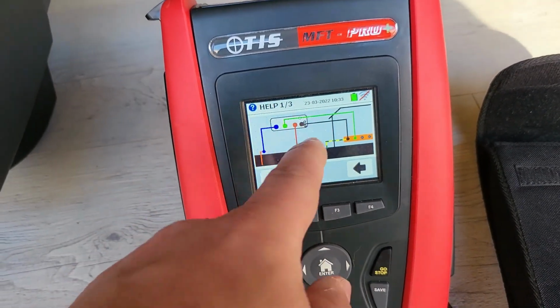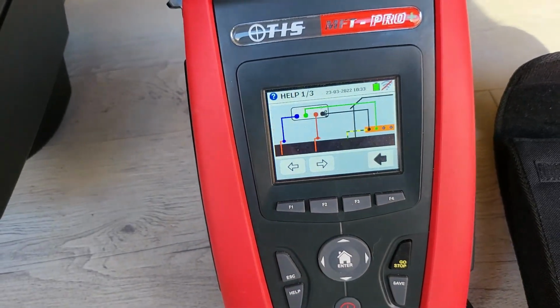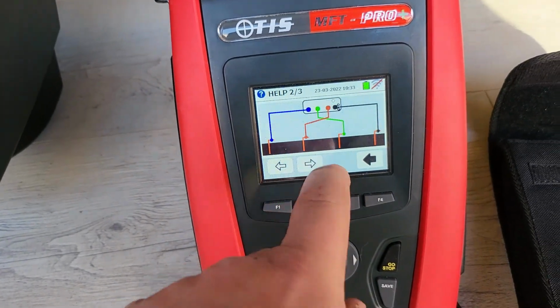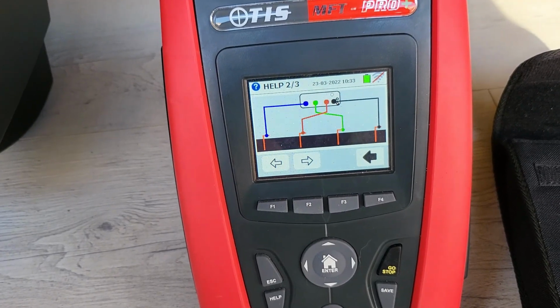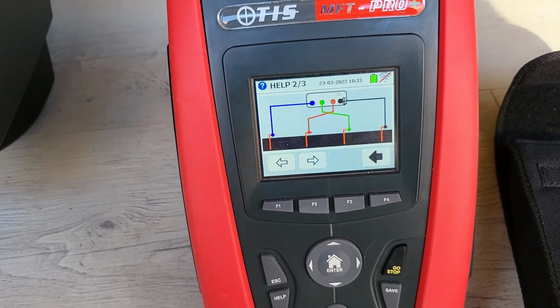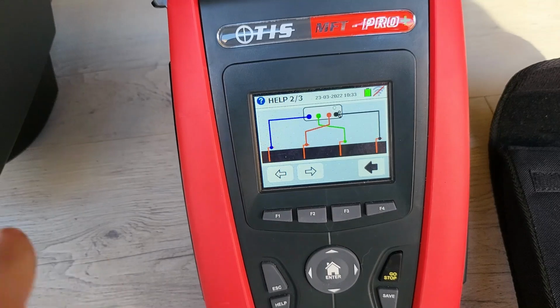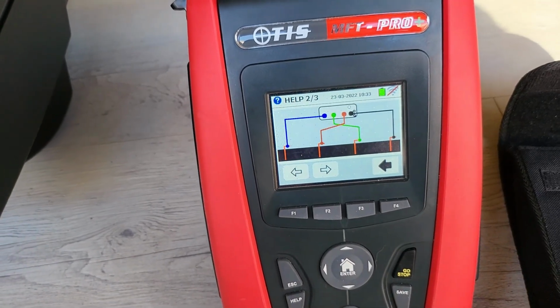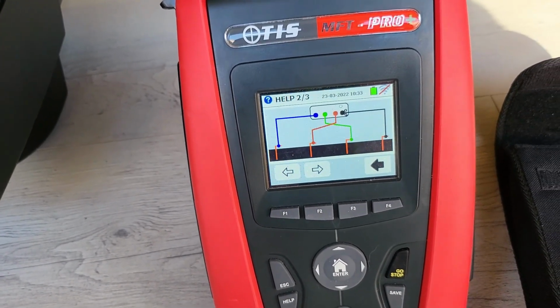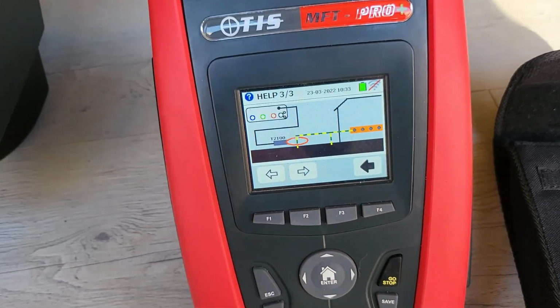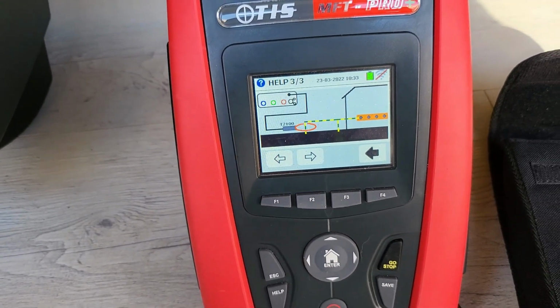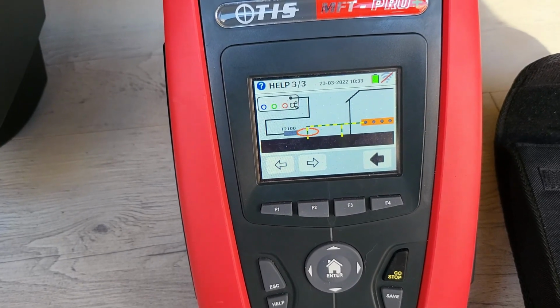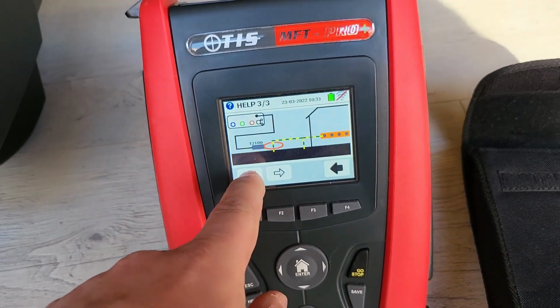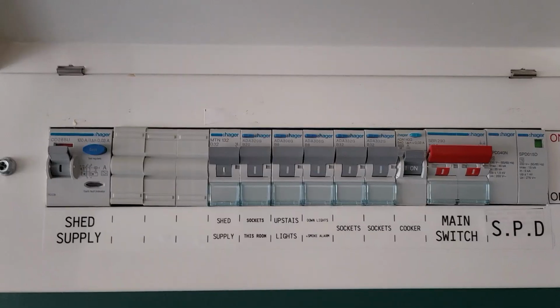And then you just move the prong in the middle around 10% in either direction, see how it affects the findings. This also does the 4-prong test, so you don't actually need an earth electrode itself. You can use the 4 prongs in the kit, which I'll show you, and just get an indication of ground resistivity. And you can also use the clamp meter as well, so you don't need to disconnect the earthing system to get your measurements. But we'll see as much as we can in the video and cover as best I can the full range of tests this thing can do. And yeah, let's get on with it.